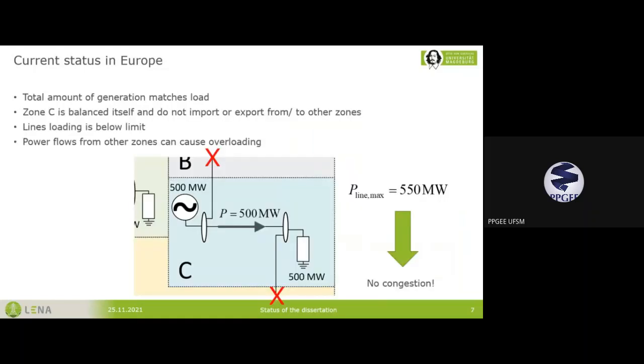Looking at zone C, a balanced zone, from a non-interconnected perspective, the generation flows directly to the electrical load, producing a power flow of 500 megawatts. Since this doesn't exceed the maximum power the line can transport, there is no congestion, so everything is fine and this zone can be operated securely.